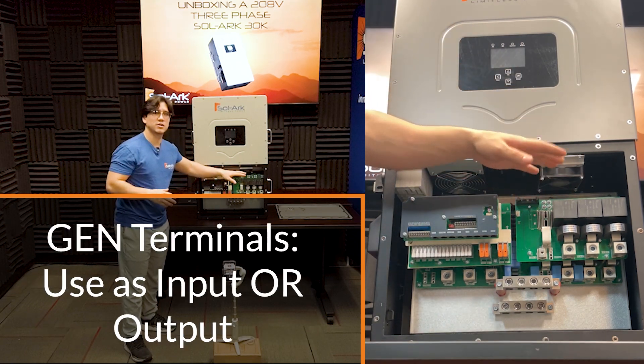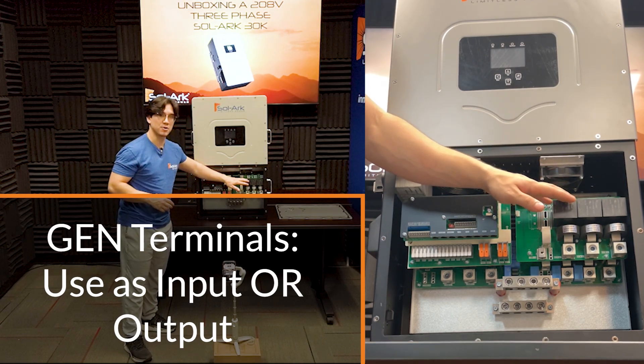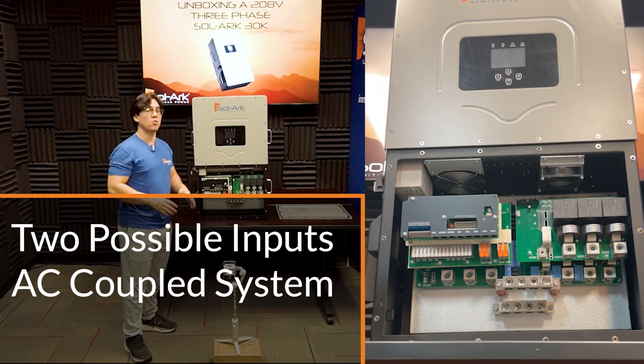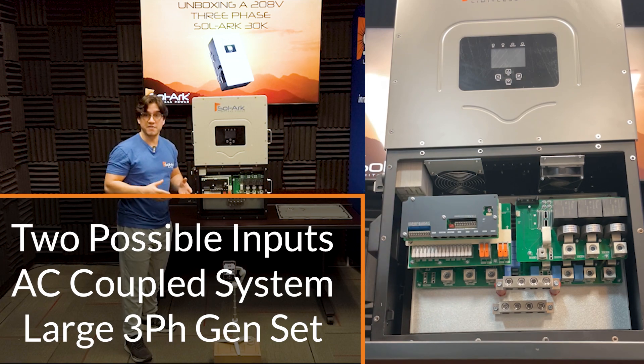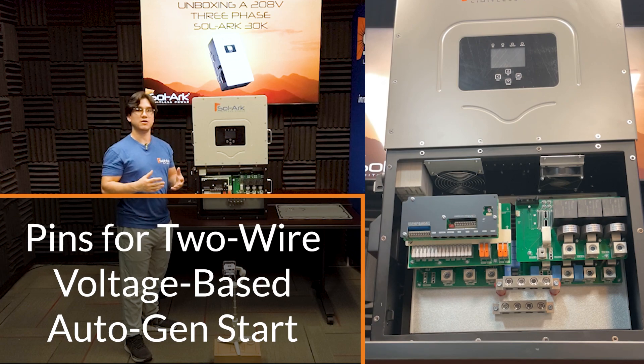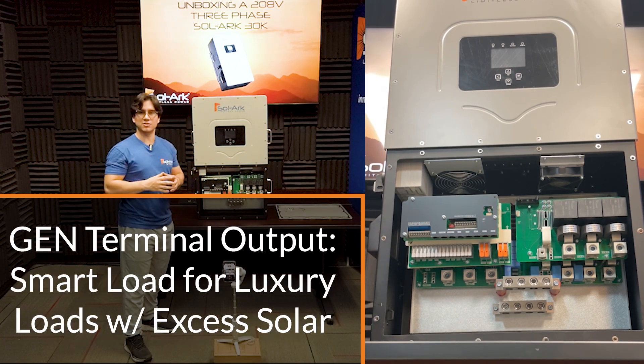On this side, we see the Sol-Ark 30K three-phase gen terminals, and they can be used as both input or output. The two inputs can be a pre-existing AC coupled three-phase system or a very large three-phase generator. Using these pin connections right here, you can use a two-wire start to turn on your generator automatically after it reaches a programmable battery voltage set point. The output can be used as a smart loads panel, which is for your luxury loads that you only want when there's surplus power. We do have an extra video on this topic available on our channel, so go ahead and take a look.